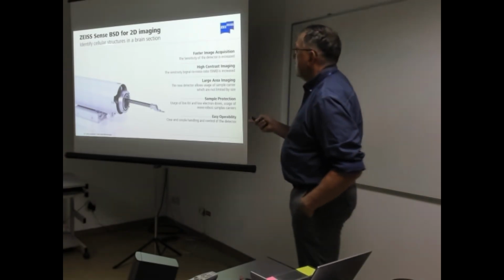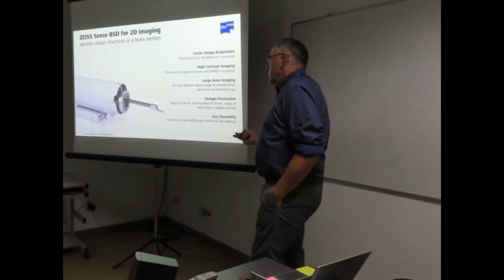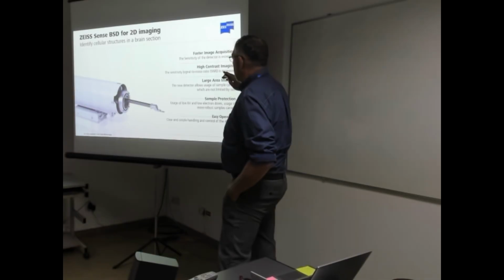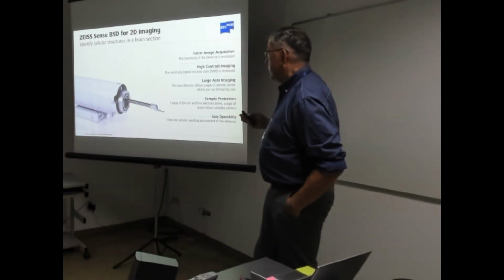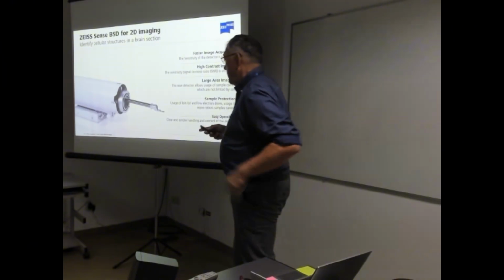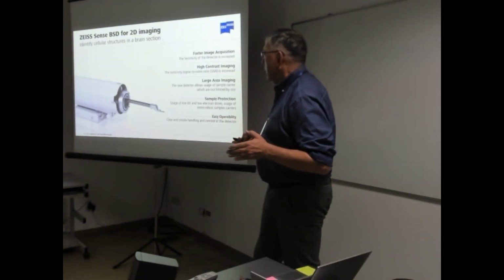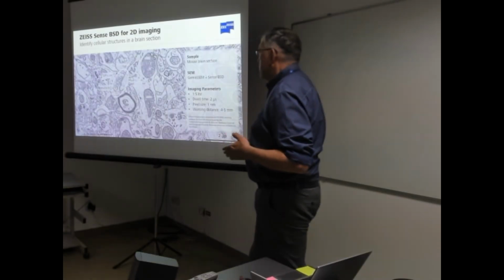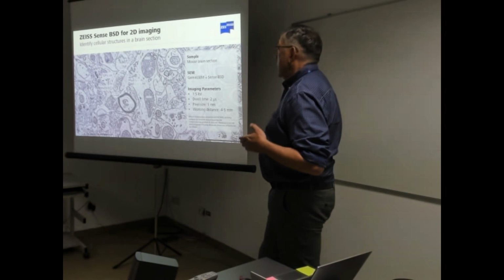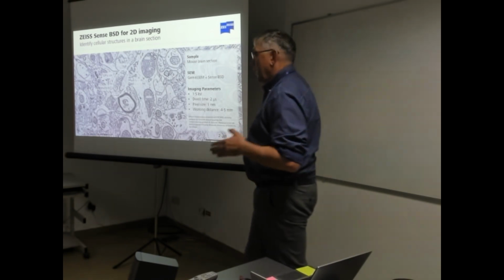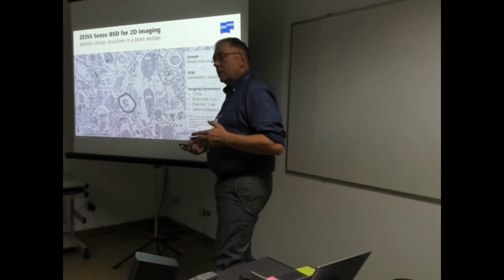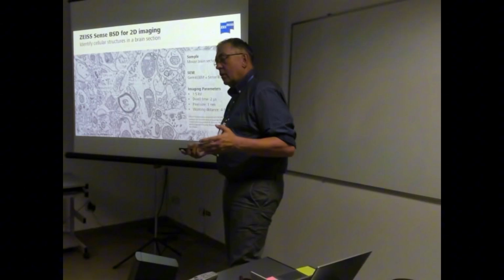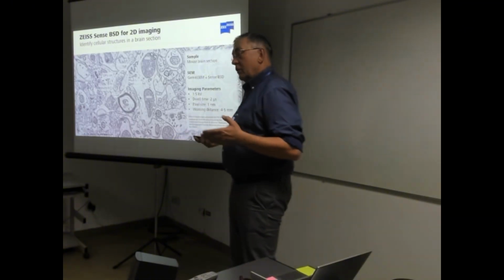We have developed a special detector, which is optimized to register the signal in the low voltage regime. What is used for this imaging is 2 kilovolt, and this detector is very sensitive and faster than the generations before, which allows us to image these kinds of serial sections faster, because scanning time is always a limitation. For these projects of 1-2 cells, we talk about scanning times of a day, 2 days, or a weekend.